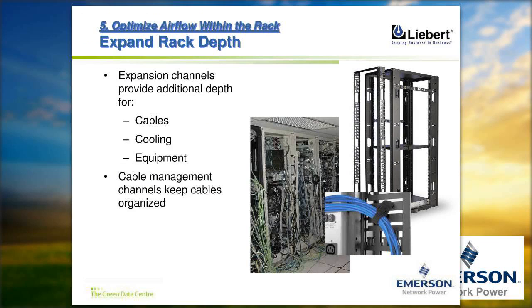Okay, it is recommended that the depth of the rack should not be just 600 by 800 or 600 by 1000. You can take a higher depth rack which will help you to manage the cable properly, so that the balance 200 mm or 150 mm behind the rack is available to dress up the cable properly, which will also not block the air and create any hotspot inside or outside the rack.